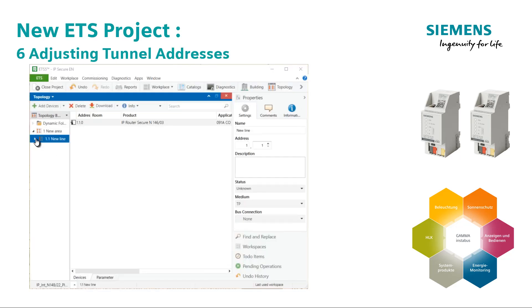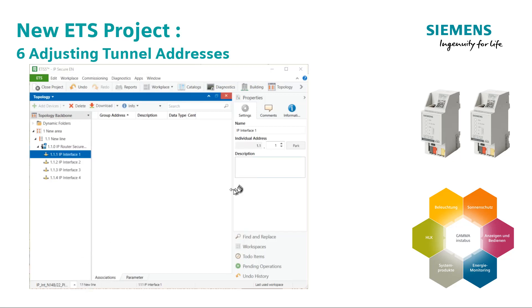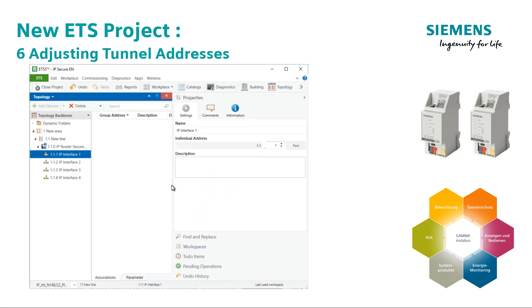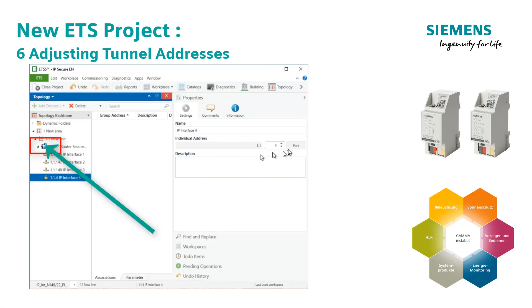Step 6: Adjust the additional physical addresses for the tunnel connections. As already known from the predecessors, when inserting IP devices with several tunnels, ETS creates physical addresses in ascending order, starting with the lowest free address. If you don't agree, you have to make these addresses visible by clicking on the small number symbol on the router's main address, and then change them manually.